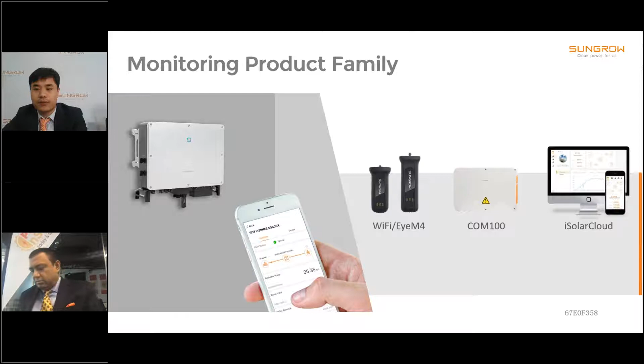This slide shows the configuration for monitoring hardware. Wi-Fi dongle connects one inverter, mainly for residential application. One EyeM4 dongle supports up to 10 inverters, with daisy chain connection between inverters where RS485 is recommended. It also has a built-in web server for management, firmware updating, and other functions. COM100 could connect more devices, up to 30, like third-party meters, weather stations, and environment sensors. Those two are suggested for the commercial market.